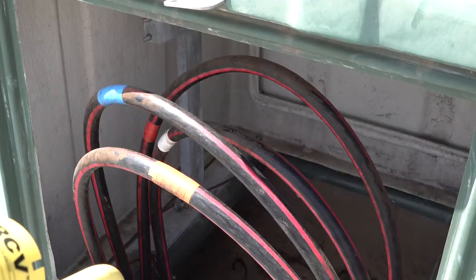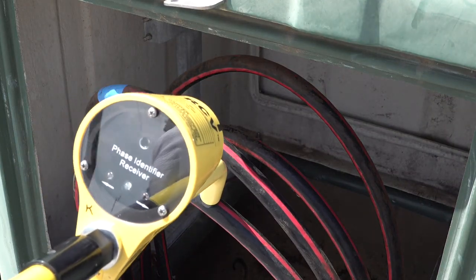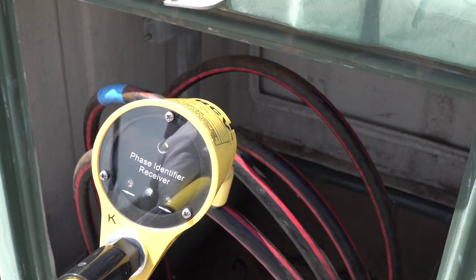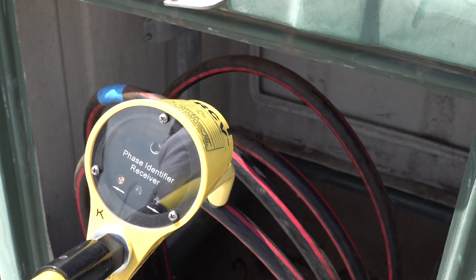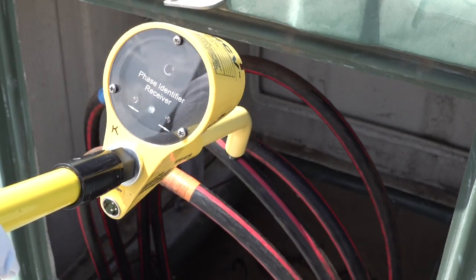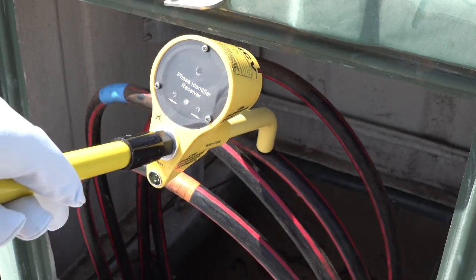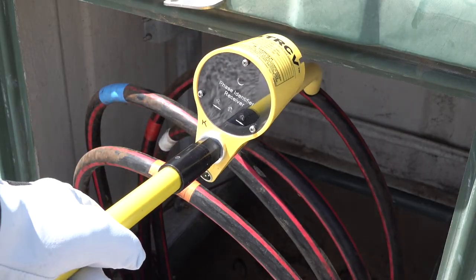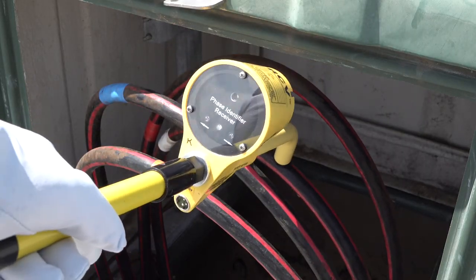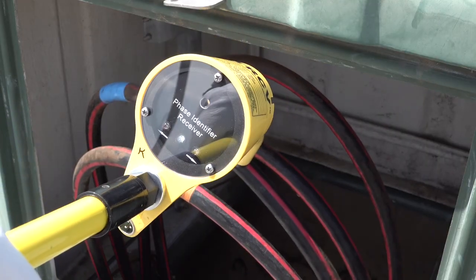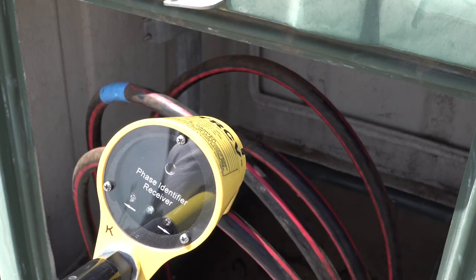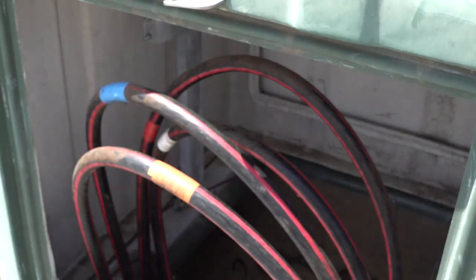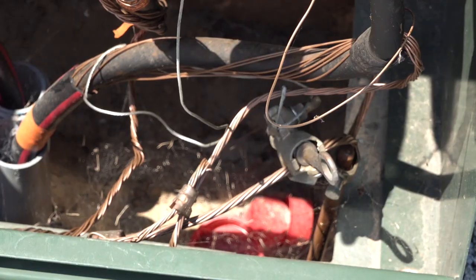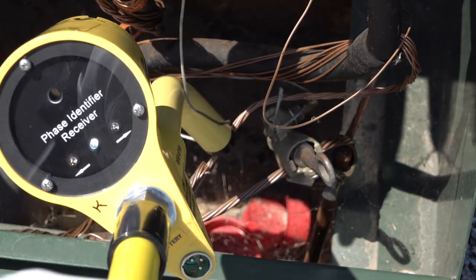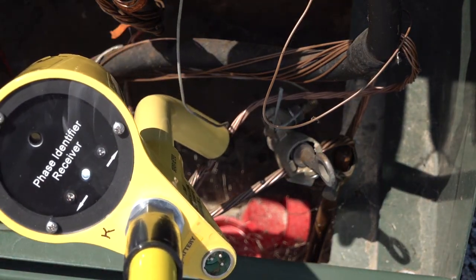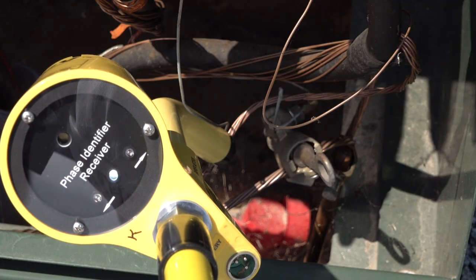Now that we've verified that the STRCV is working properly at the near end, we can go out to the location to identify the de-energized primary cable. By looping all the primary cable up in this dog box, it replicates a manhole or a ditch. With the STRCV still in the low current setting, check each cable and verify which cable has the pulse on it. As you can see, the orange cable has the pulse and is our de-energized primary cable. We can also go to the endpoint of the de-energized isolated primary cable and verify the concentric pulse there as well.